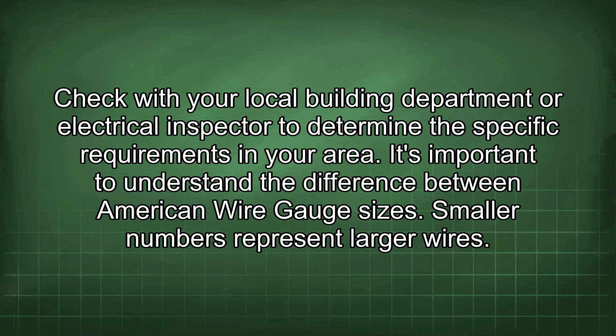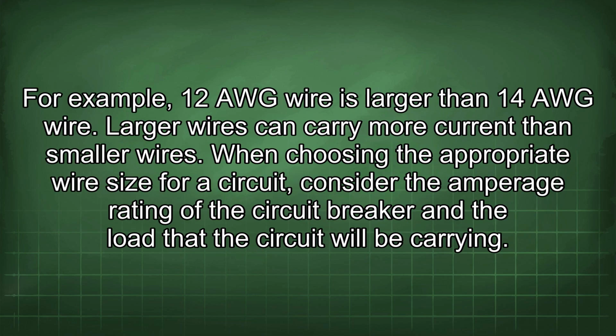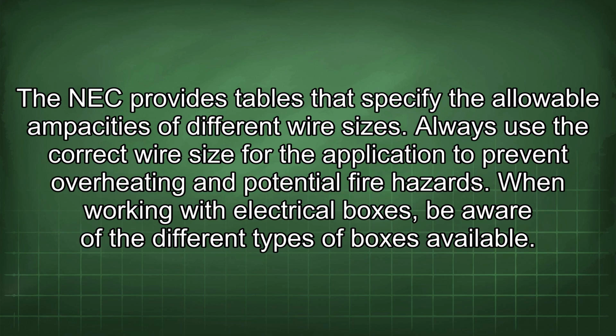It's important to understand the difference between American wire gauge sizes. Smaller numbers represent larger wires. For example, 12 AWG wire is larger than 14 AWG wire. Larger wires can carry more current than smaller wires. When choosing the appropriate wire size for a circuit, consider the amperage rating of the circuit breaker and the load that the circuit will be carrying. The NEC provides tables that specify the allowable ampacities of different wire sizes. Always use the correct wire size for the application to prevent overheating and potential fire hazards.